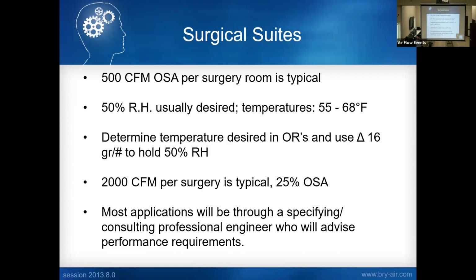Typically we see about 500 CFM of outside air per surgery room. Typically you see temperatures of about 55 to 68 degrees at 50% RH. I've seen from experience, we had one operating room where we were going 40% to about 60% RH, and it really depended on the surgeon more than the operation or anything. We'd have one surgeon with one condition, another surgeon with another condition.